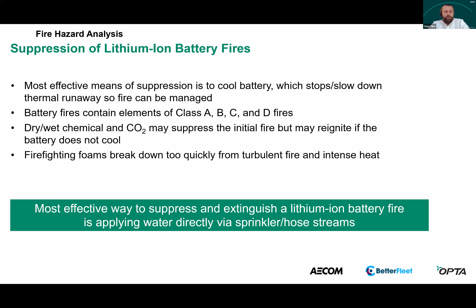To extinguish a fire, we need to be able to remove one of the three legs of the fire triangle: either fuel, oxygen, or heat. And we can't remove the fuel since the battery electrolyte itself is flammable. Testing has shown that smothering a battery fire to starve it of oxygen is not effective when applying an agent like a dry chemical powder, which leaves us with cooling the fire as our best means of being able to control these fires.